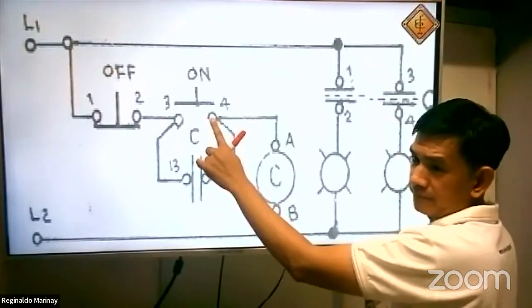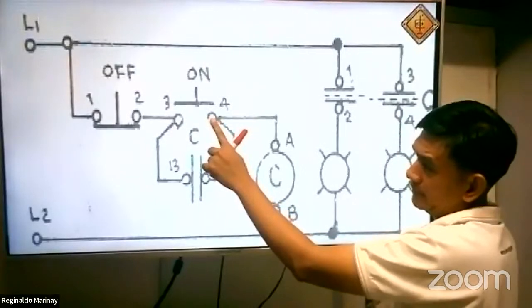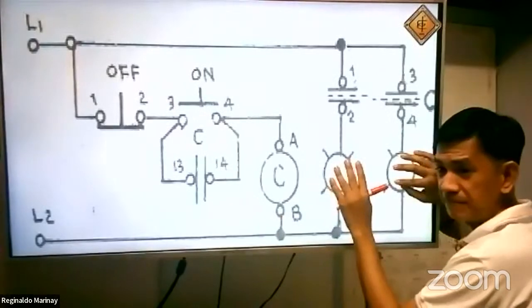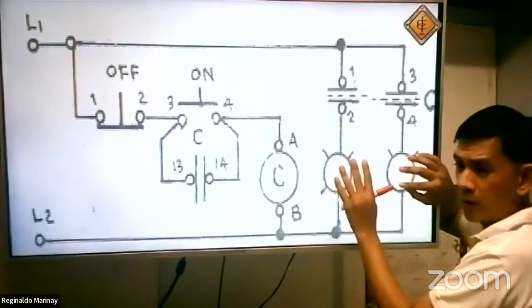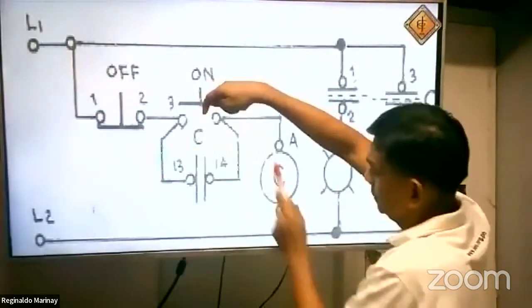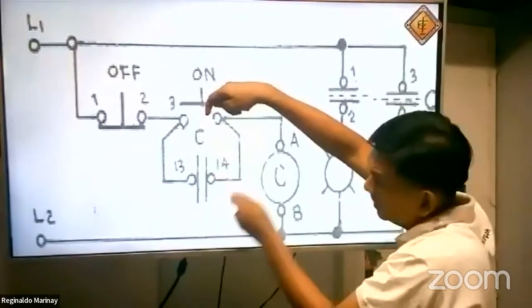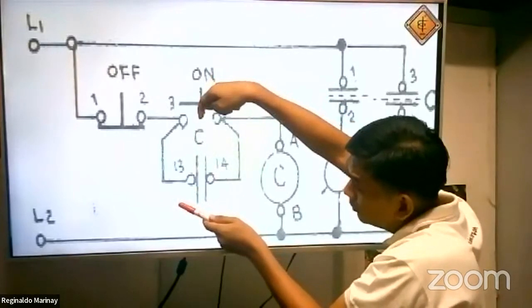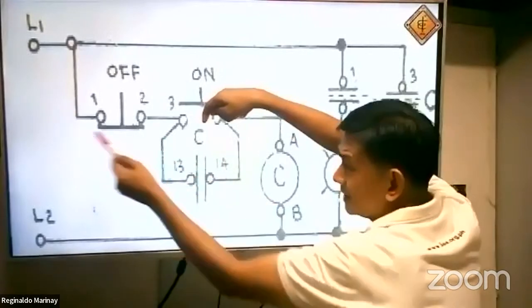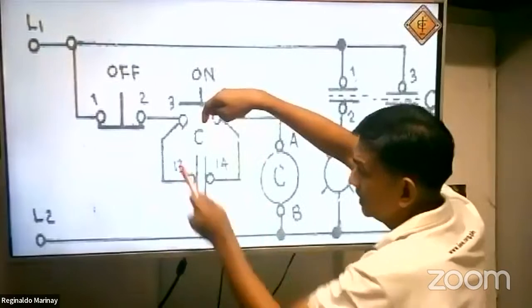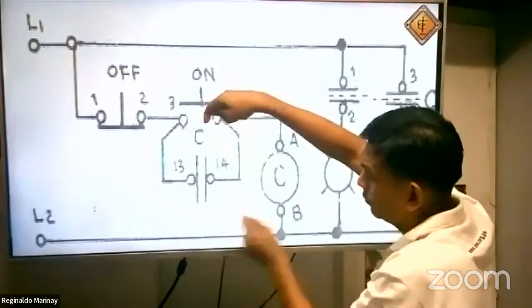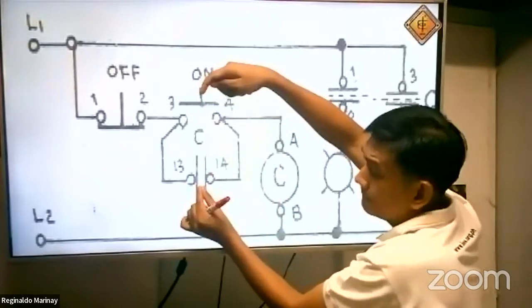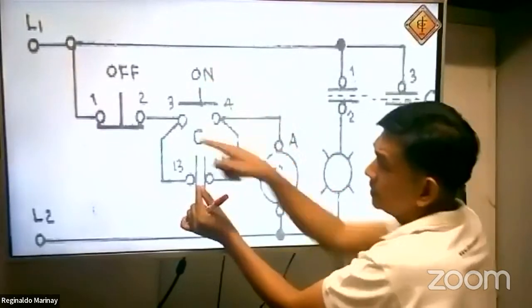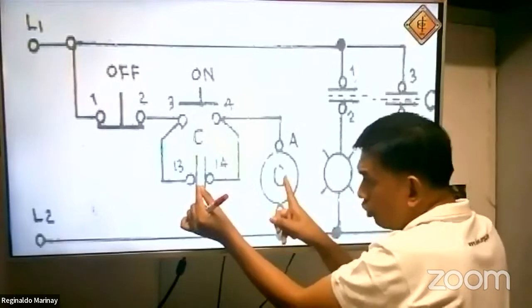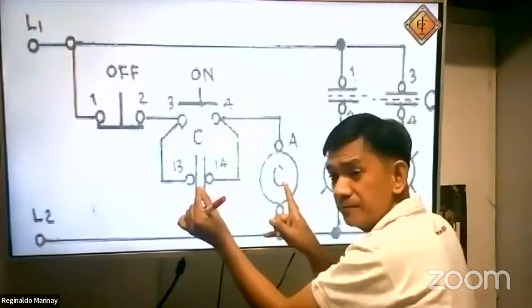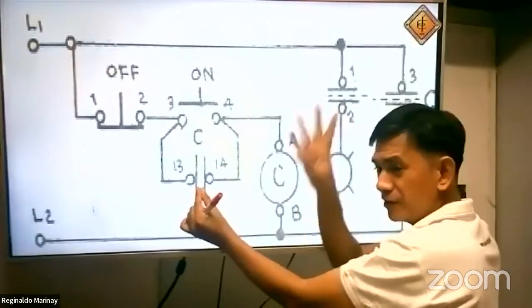Question. Would that mean if this becomes open, this is already de-energized? The answer is no. The answer is no. Why? Because once we press this push button, energizing your holding coil C, this will become closed. Once this becomes closed, you release this push button. Once this becomes closed, the current is still flowing here. The current is flowing here, energizing your holding coil C, because this becomes closed. Even though you release your finger here, pop, this is continuously energized. As long as there is current flowing to this holding coil, this will continuously be closed. That is the idea. I hope you're getting me.